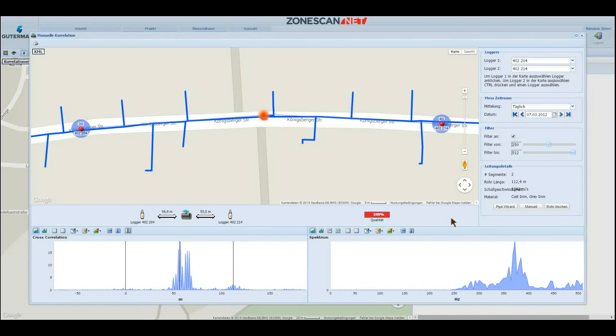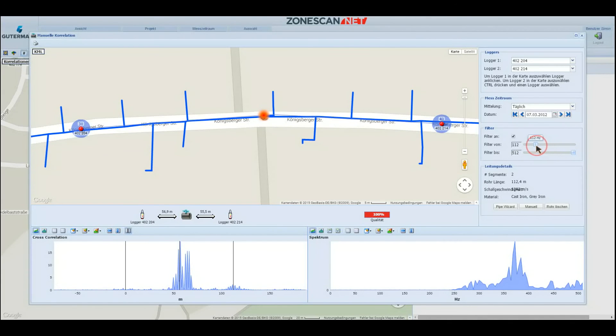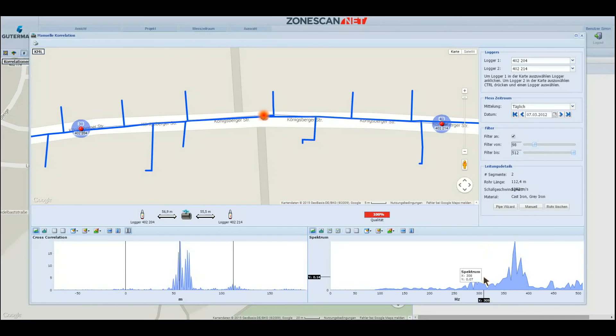As you can see, the correlation is now located in a different spot, almost exactly on the hydrant in the middle, which is where the leak was actually located. In addition to that, you can try different filter settings in real time. As soon as you let go of this switch, the correlation is relocated based upon the new filter settings. This tool is very useful when dealing with noises that aren't leaks, for instance PRVs.